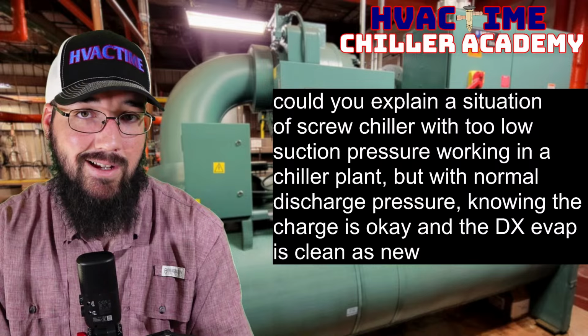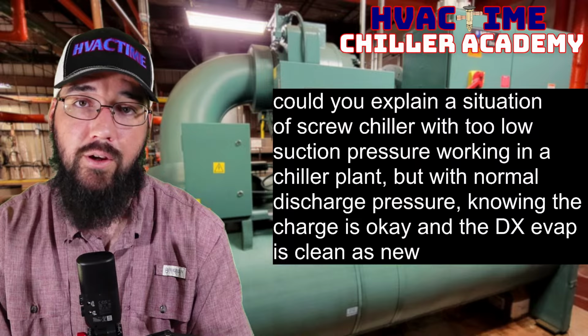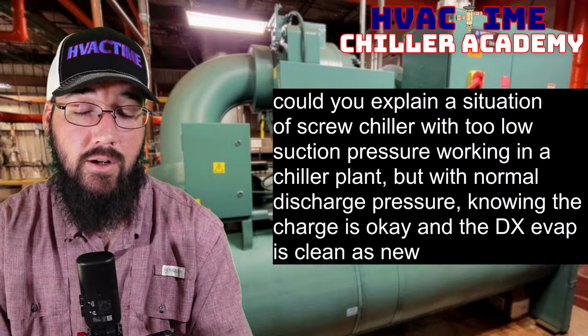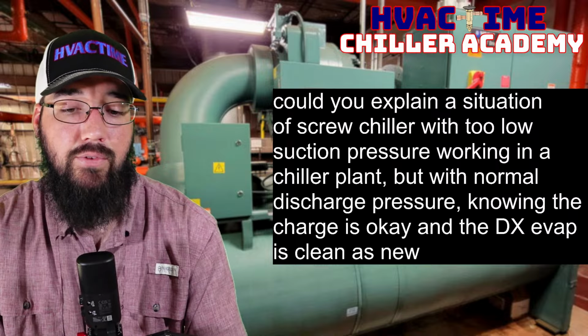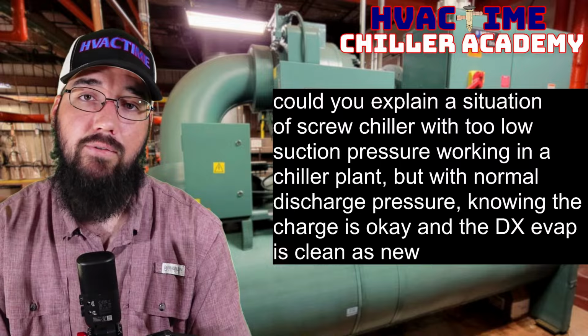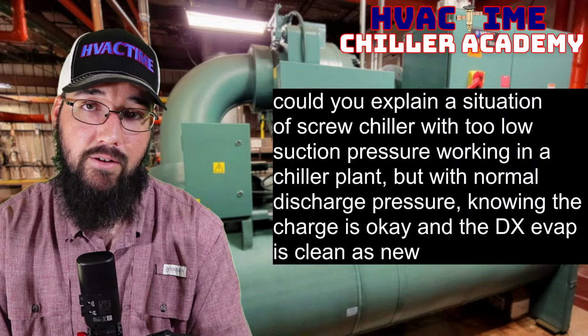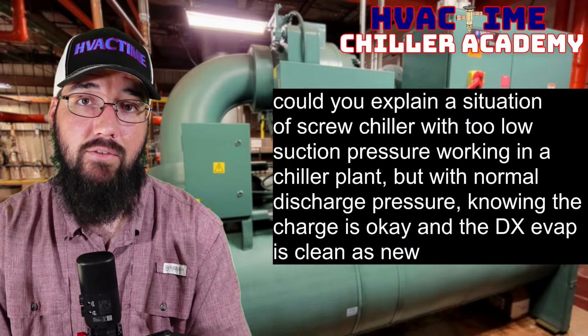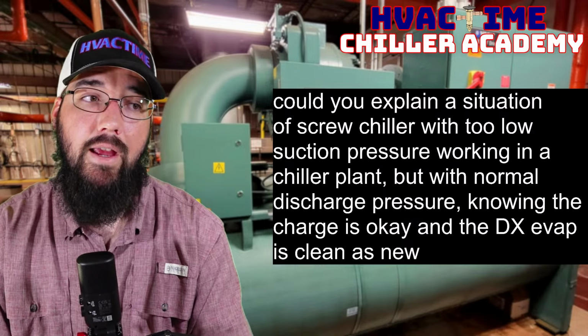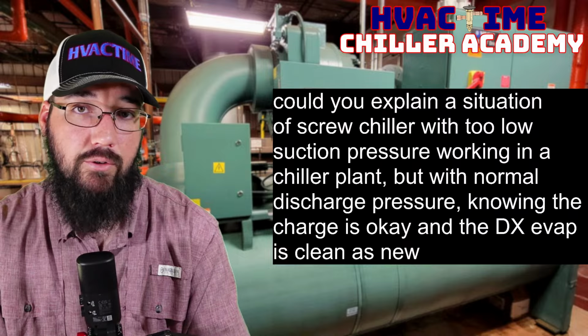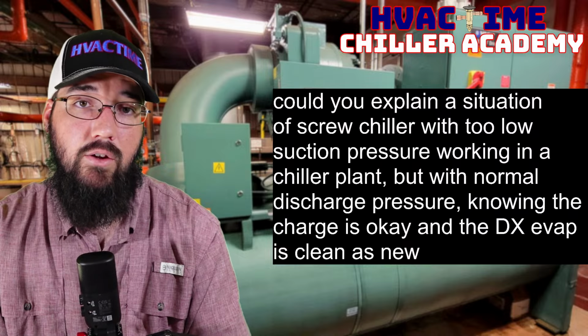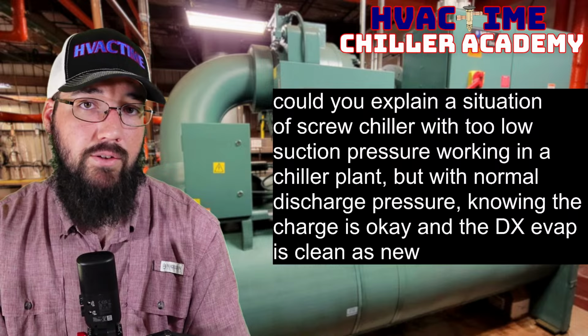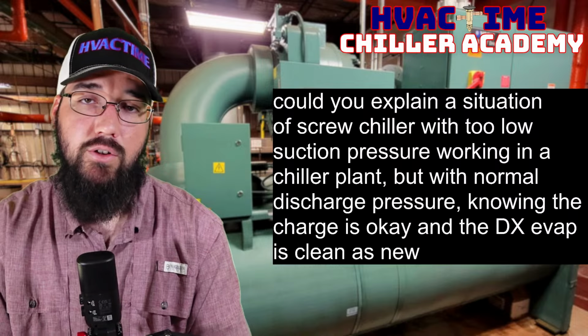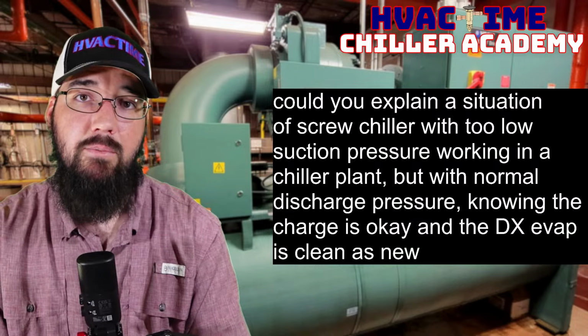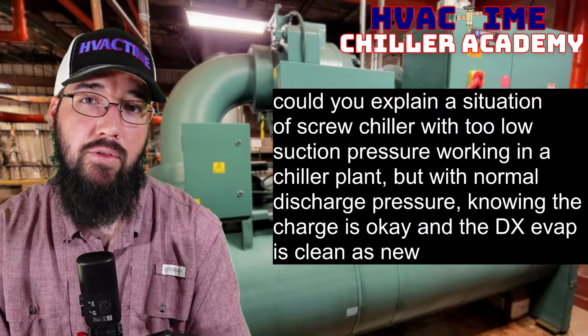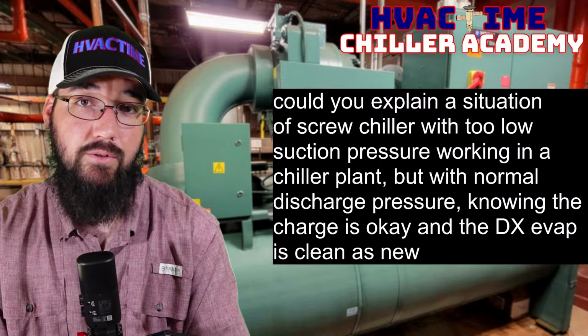I see this a lot where facilities want to run 40, 42 degrees of leaving water temperature. That's fine if that's what the facility needs, but depending on the style of evaporator you have, if you've got a DX style evaporator and you're trying to run a 40 degree leaving water temperature, well, water freezes at 32. Most chillers will have a suction limiting set for about 34, 35 degrees of saturation.